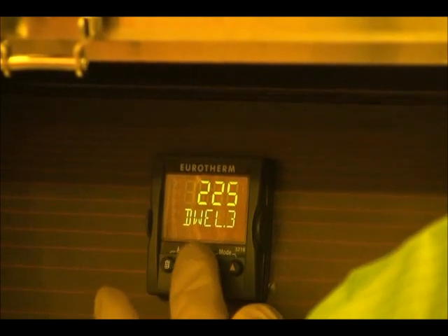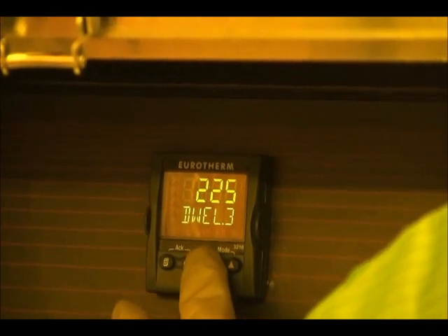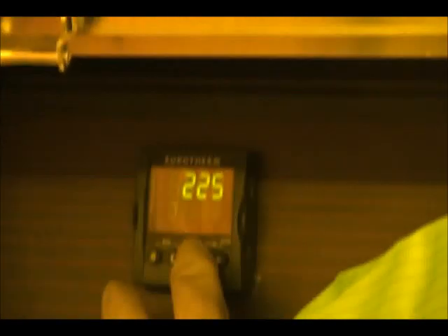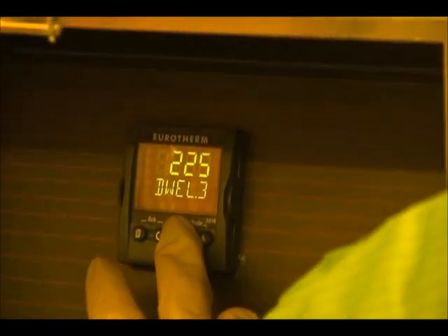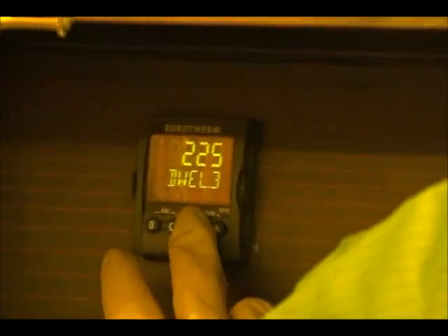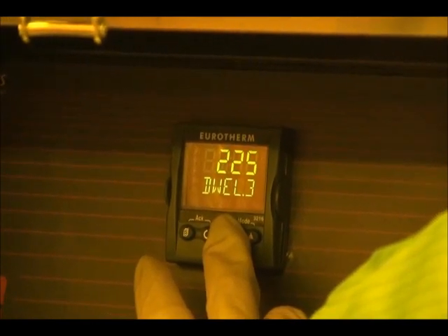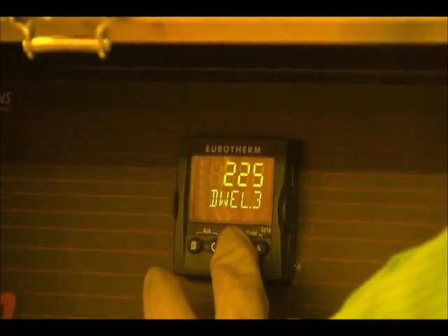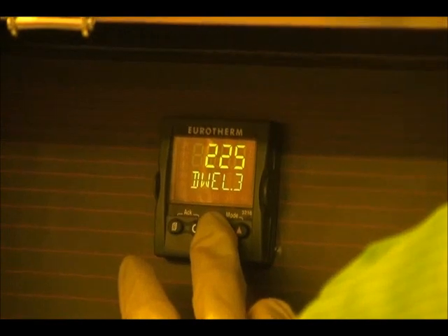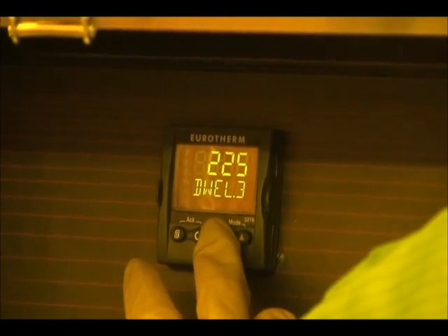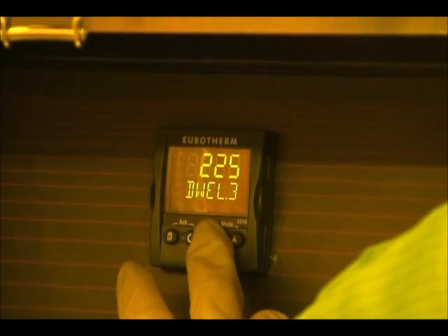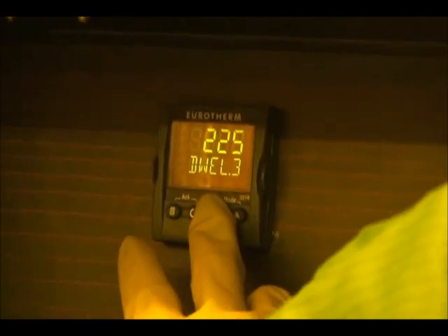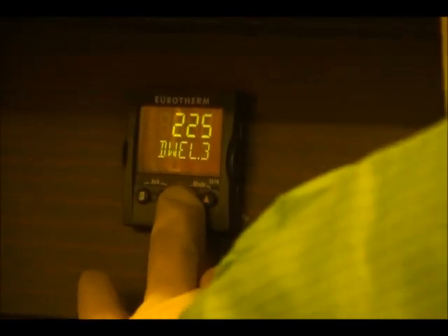Now this is dwelling time 3. We will make the wait time 40 minutes because we want to do the wet oxidation at 1000 degrees for 30 minutes. It's up to the thickness we want, but we need 10 more minutes to make the temperature at 1000 degrees stable. So the total dwelling time is 40 minutes. So now we change the dwelling time 3.